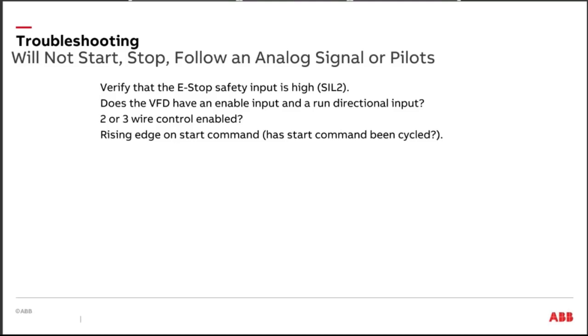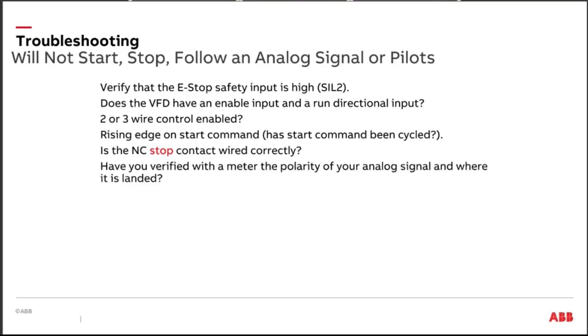I think about, is there any chance that somebody has tripped my safety interlock circuit and the drive is not starting? Do we have the drive set up for 2-wire or 3-wire control? Does the drive require a rising edge? Was the drive running and power went down, and now I'm going to have to cycle the start command before it starts back up? Okay, I think about that. I've seen issues like that. I look at the contacts. It's not uncommon that we see people on the wrong side of the contacts. Okay, that's actually fairly common.